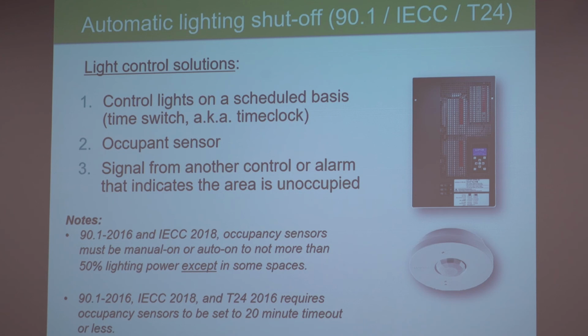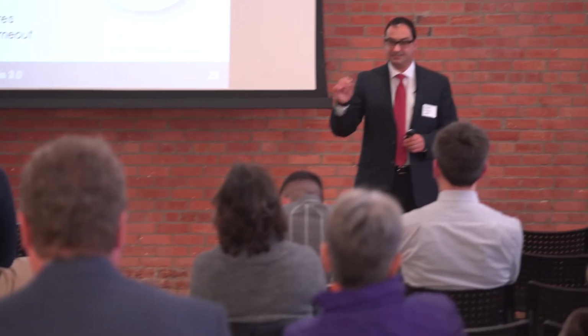Was there still the same exceptions, like the 24/7 space, or where there might be a personal safety factor? Yes, so there are exceptions that still exist for that. 24/7 is one of them. So I'm giving you the higher level stuff, but there are going to be some exceptions that affect this. Key notes here, though, that in most spaces, you either have to use partial automatic on sensors or vacancy sensors, okay? And then the 20-minute timeout now is in the latest version of these energy codes, okay?